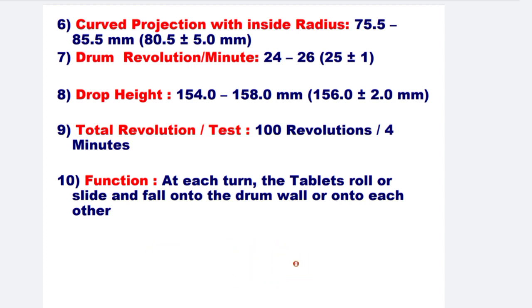Number 7: drum revolutions per minute — 24 to 26. Number 8: drop height — 154 to 158 mm. Number 9: total revolutions per test — 100 revolutions per 4 minutes. Number 10: function — at each turn, the tablets roll or slide and fall onto the drum wall or onto each other.